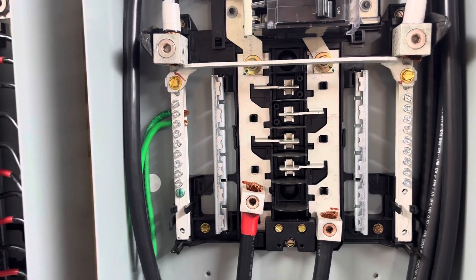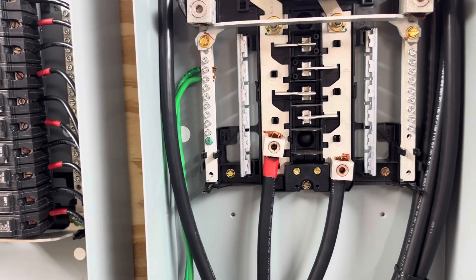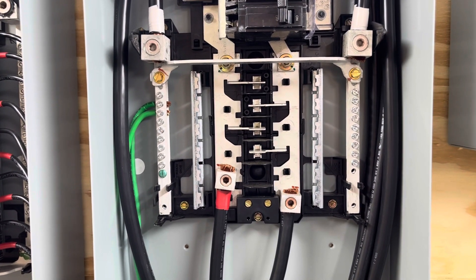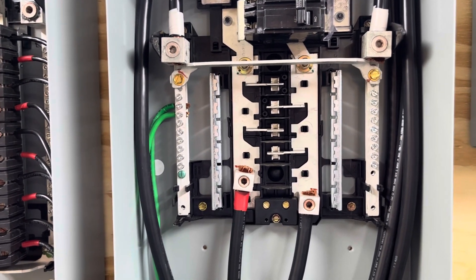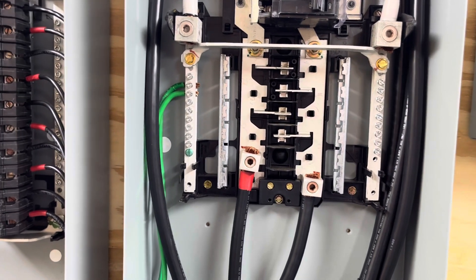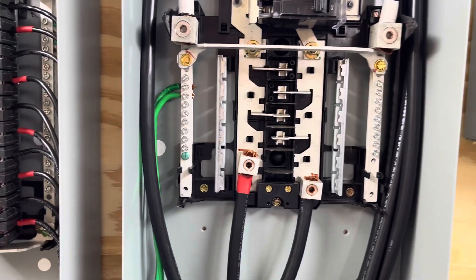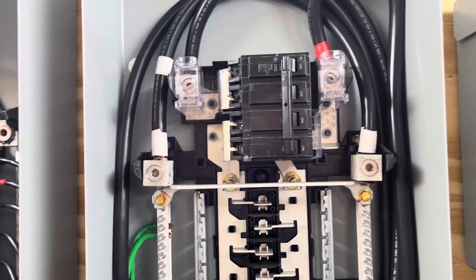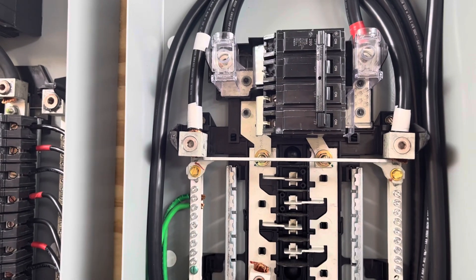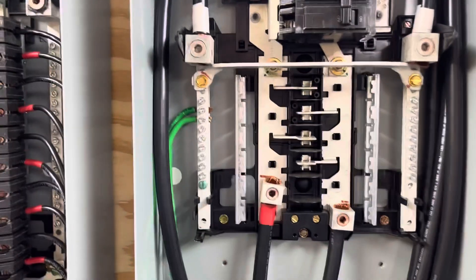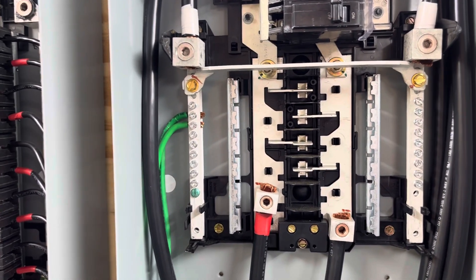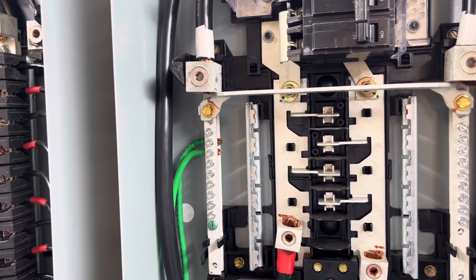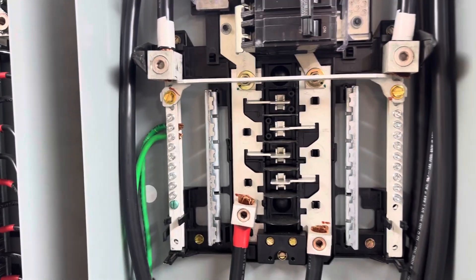Now I can do that because the primary side and the secondary side of the transformer is isolated. That means L1, L2 on the primary side is isolated from L1, L2 on the secondary side, and I've derived the neutral. It's called a separately derived neutral. And in that case, my first panel on the load side of the separately derived neutral from the transformer, the ground is bonded, or the neutral is bonded to the ground. So that's what I've done.